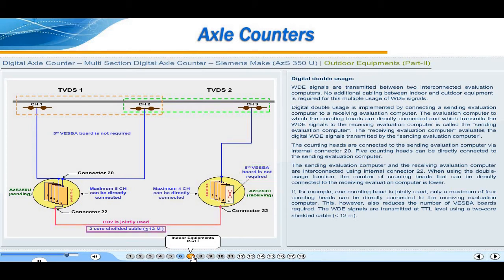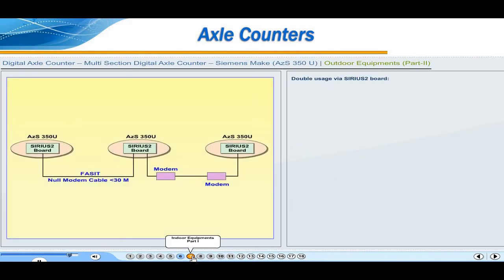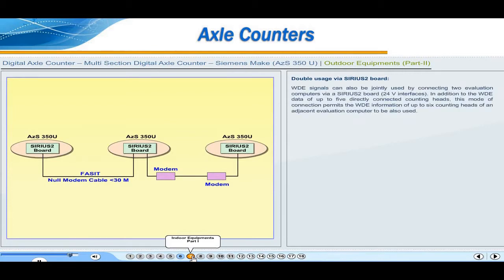The WDE signals are transmitted at TTL level using a 2-core shielded cable that is less than or equal to 12 meters. Double usage via SIRIUS2 board. WDE signals can also be jointly used by connecting 2 evaluation computers via a SIRIUS2 board, that is 24-volt interfaces. In addition to the WDE data of up to 5 directly connected counting heads, this mode of connection permits the WDE information of up to 6 counting heads of an adjacent evaluation computer to be also used.